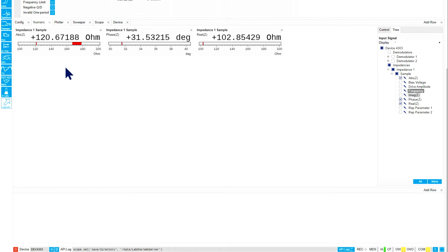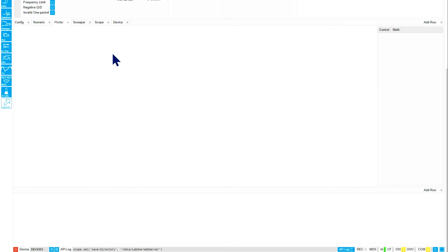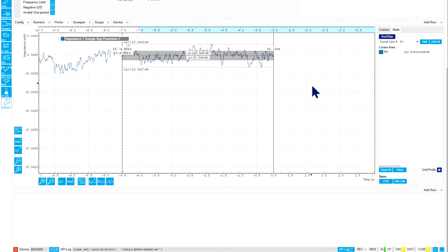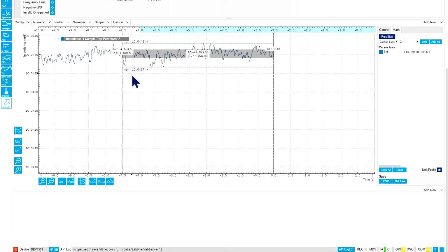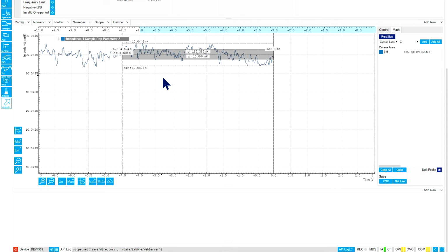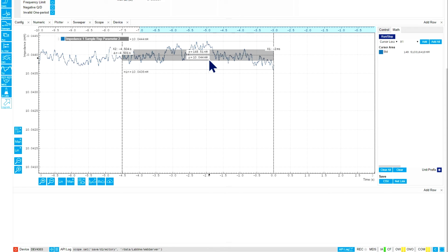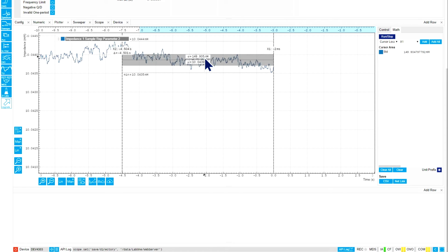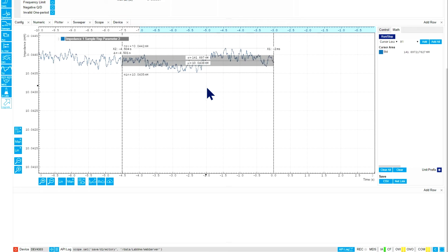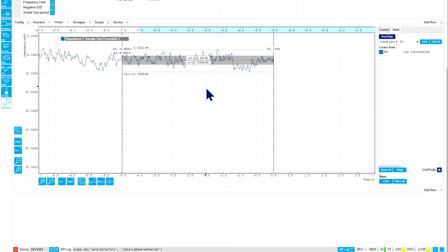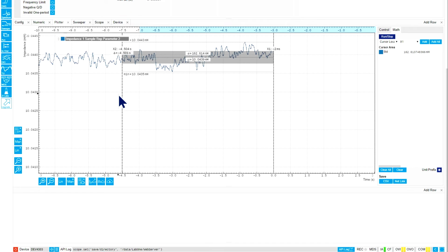Now, do you want to see beyond numbers and analyze impedance changes in the time domain? The plotter function of MFIA is here. This function helps you to track the signal changes in real time with a time resolution of up to 10 microseconds, and you can directly read off the mean and the standard deviation of the measurement. This is a very useful feature to check the warm-up of the device and to see if the device is otherwise changing with time, for instance, in sensing applications.